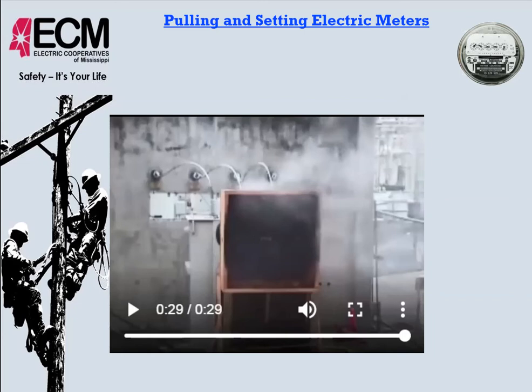One thing I want to make clear is that meters are not switches. There's an OSHA standard that says we should not make or break connections unless we do so with a load break or load make device, and meters are not one of those. This is contrary to the way I was trained. I was trained that if you think there's a lot of load on it when you're pulling it, pull it fast, and if you think there's going to be load you'll pick up, set it fast. That is not correct. That is improper training.